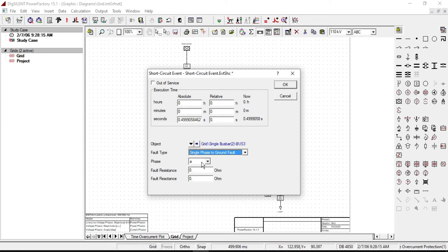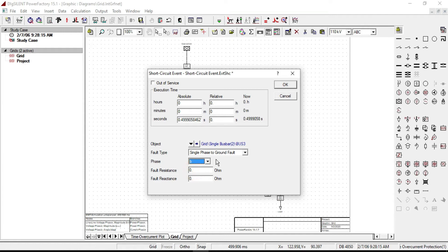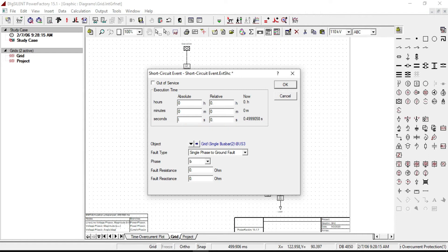From here you can select either phase A, B, or C. Let's say the fault will occur on phase B. You can also determine the fault resistance, but in this case I will leave it at zero. Assume the single phase to ground fault on phase B occurring at 0.4 seconds. Click OK.